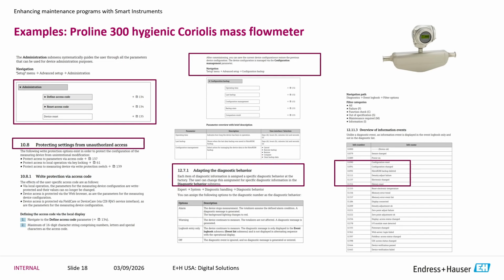If it's critical versus non-critical, I'm able to pass that information through my Rockwell PLC, make that flash on Factory Talk Historian to say a maintenance engineer changed the configuration of this tag on this date and time, here is what they changed. Do you want to revert to the previous configuration, or analyze what the proper action is to take with that device?